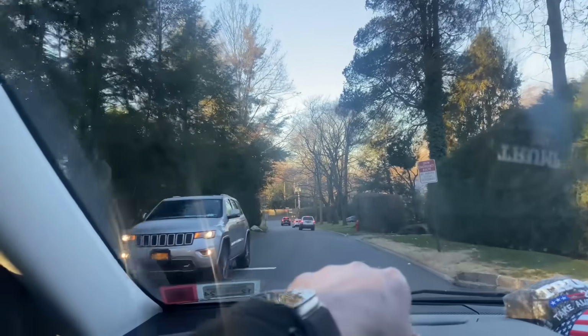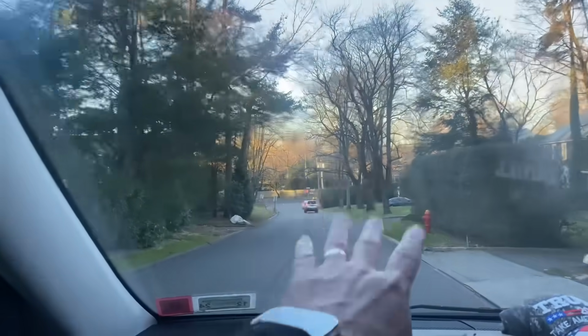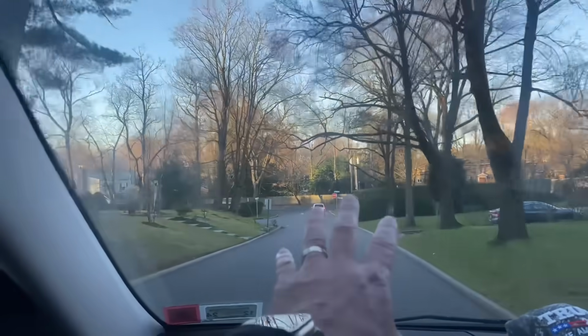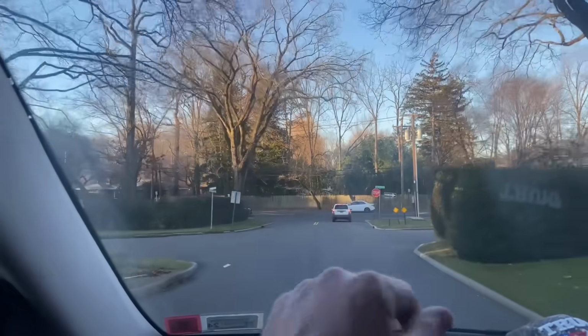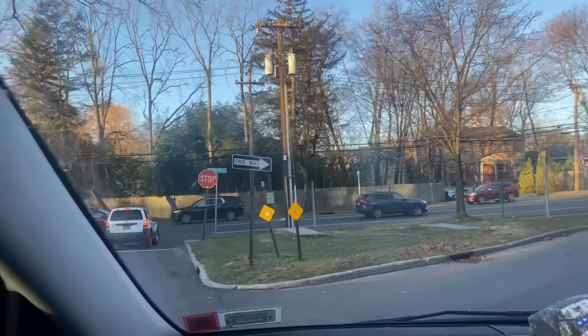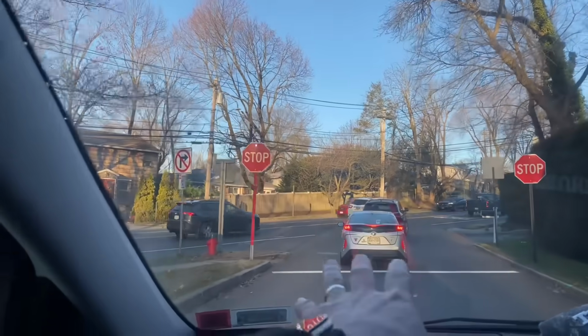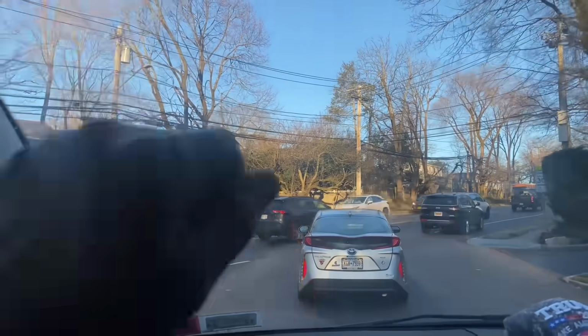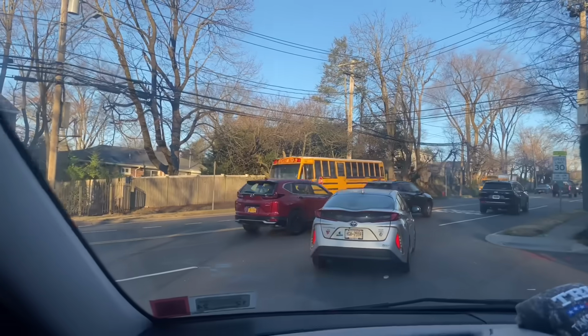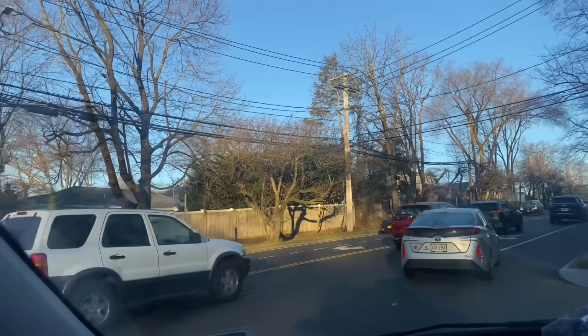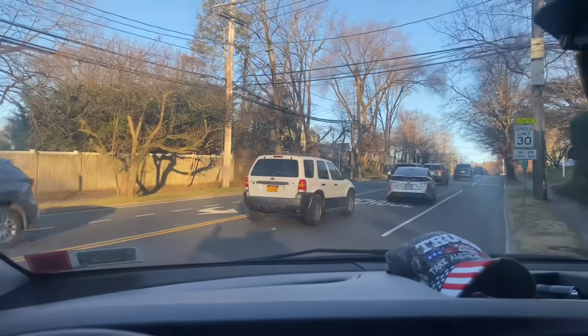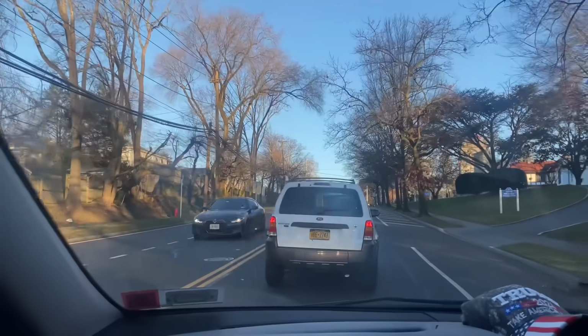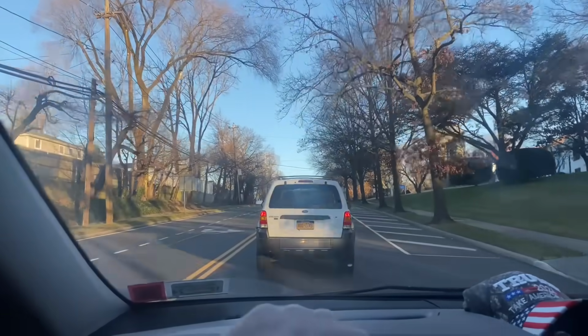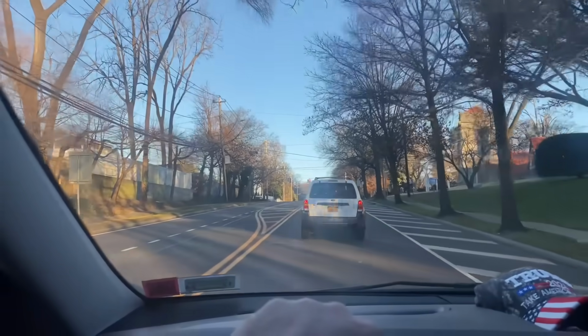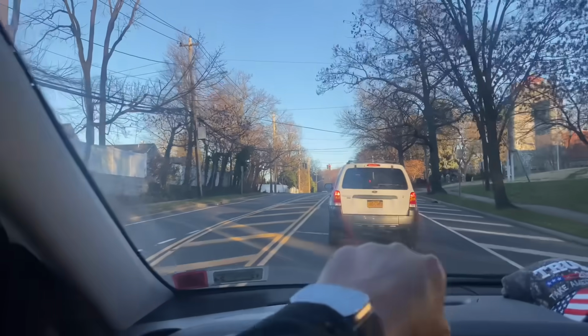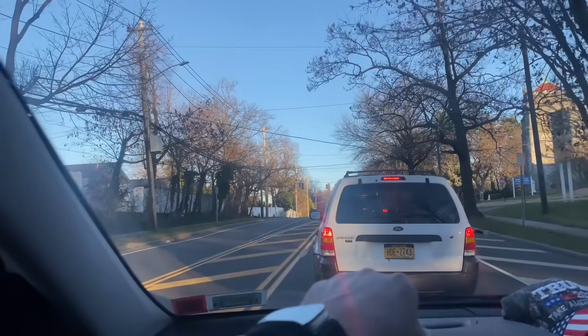This morning, we are heading to an existing property but new client who's got a Bosch Greenstar, not a wall hung, but a floor mounted boiler. We have another contractor who was out there for this new homeowner. We've been servicing this boiler in the past. We didn't install it, but apparently they replaced the external circulator and the internal circulator, and it's still not working. So we're heading to Port Washington. Port Washington is on the North Shore, part of what they call the Gold Coast of Long Island, in the great state of New York.